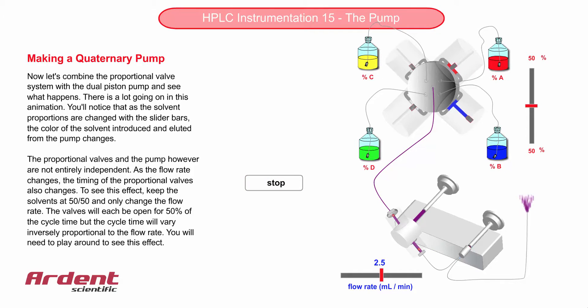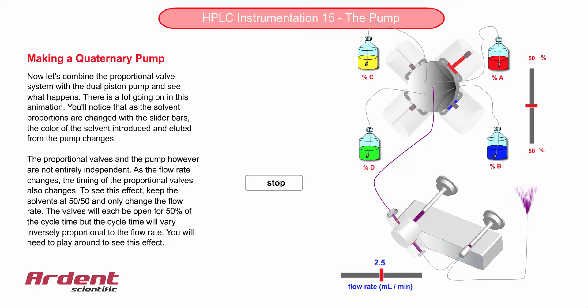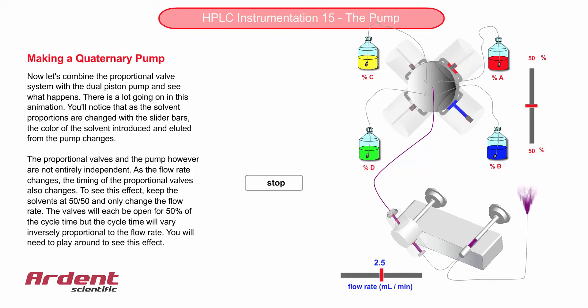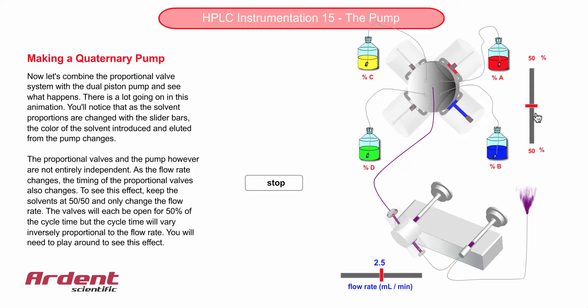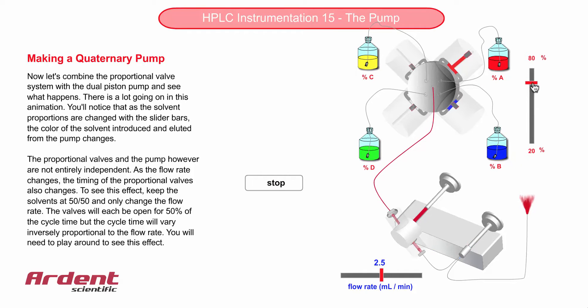Now is the time to put all this together to make a quaternary pump. You can use the slider bars which are next to the solvent bottles to change the mobile phase proportions, but also in this animation you can change the flow rate which will change the piston stroke timing.